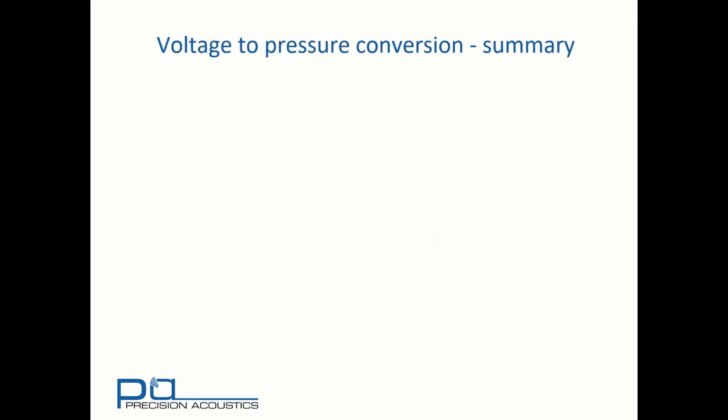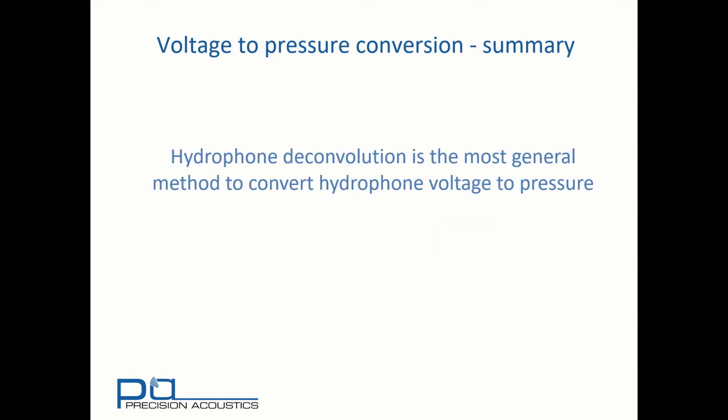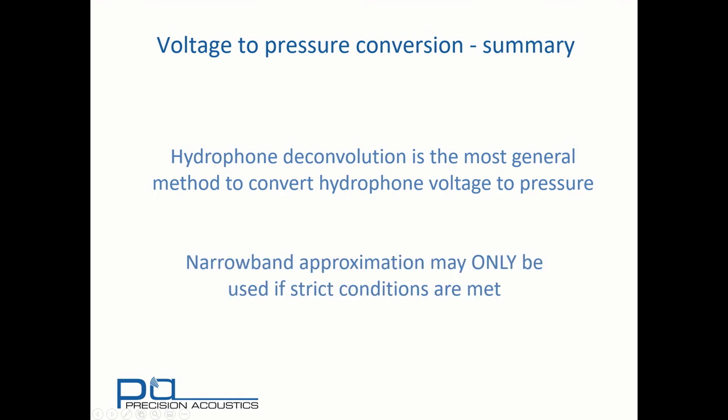So to conclude, hydrophone deconvolution is the most general method to convert hydrophone voltage to pressure. The narrowband approximation may only be used if the strict narrowband conditions are met. We hope you found this interesting. If you did, come back and find some more of the Precision Acoustics tutorial videos.